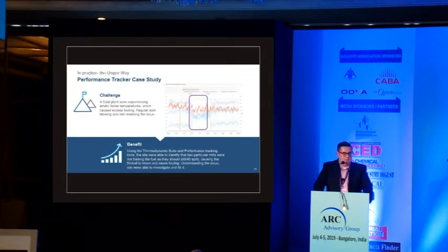Another example, this is from our colleagues in Australia. The plant is a mine mouth facility, and they were experiencing erratic temperatures in their boiler, causing excess fouling, particularly around the top of the boiler. They were doing regular soot blowing, but this wasn't resolving the issue.